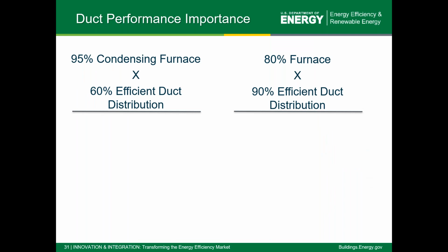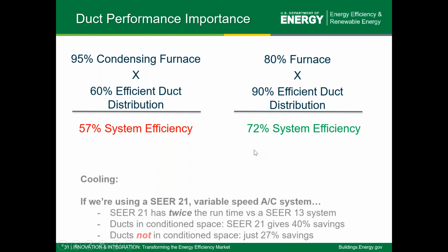A quick example of why duct location can really matter is shown here. On the left, we might have a very efficient furnace but a pretty unimpressive duct system at 60% efficiency. On the right, we have a very minimal efficiency furnace but a very efficient duct system. If you combine those two, the overall system efficiency is better with a routine furnace but a great duct system. In reality, we want the best of both worlds: good HVAC efficiency as well as good duct efficiency. But this emphasizes why duct location and performance is really important.